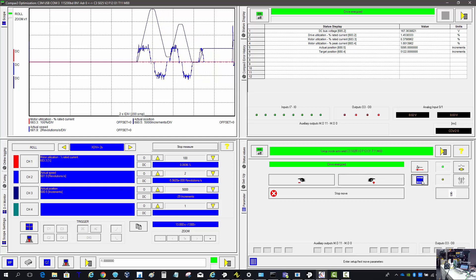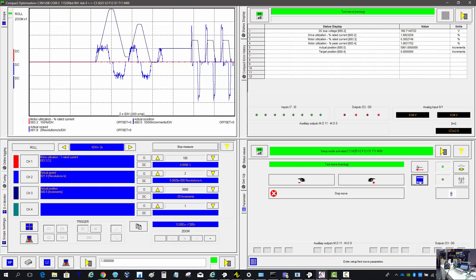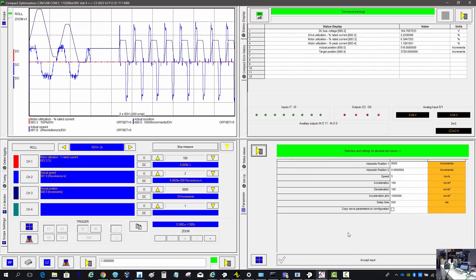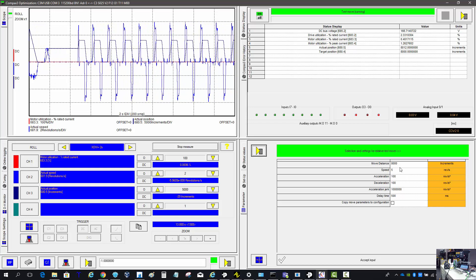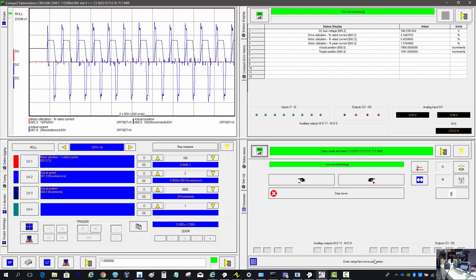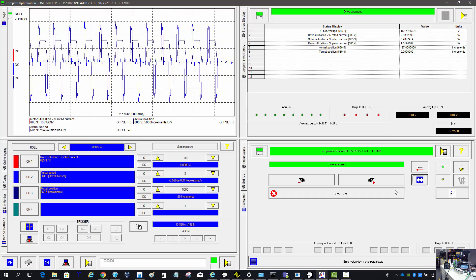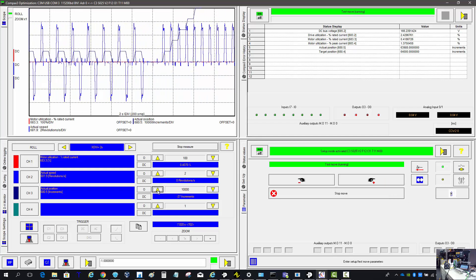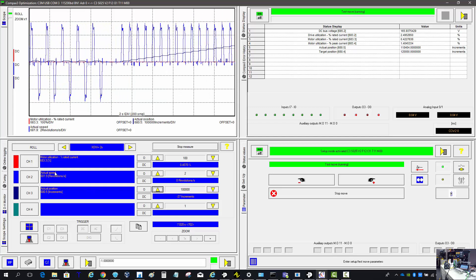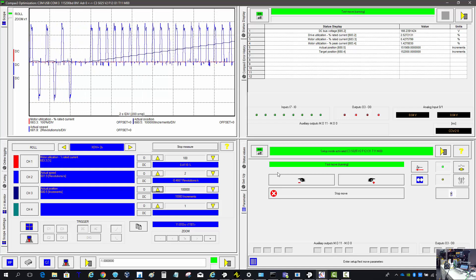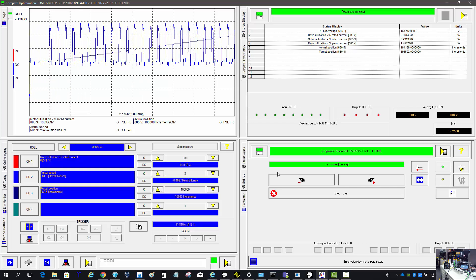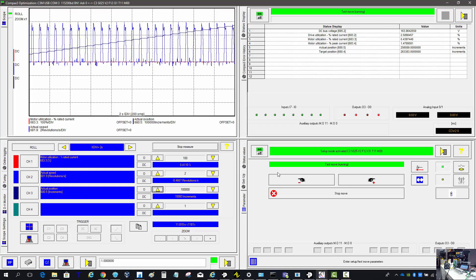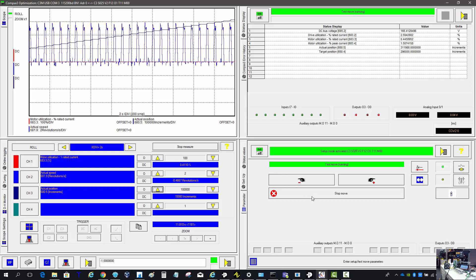If you want to move to the zero position or move back and forth, that's the absolute test move between two position points. You can also set up a relative test move which runs continuously with a time delay between moves — that appears as two forward-arrow icons. Note that the position keeps incrementing in that mode, so you may want to change your scaling; that's why I like to look at actual speed on the scope. I'm not going to get into tuning here — there's a separate video on tuning and auto inertia detection on both rotary and linear servo motors.